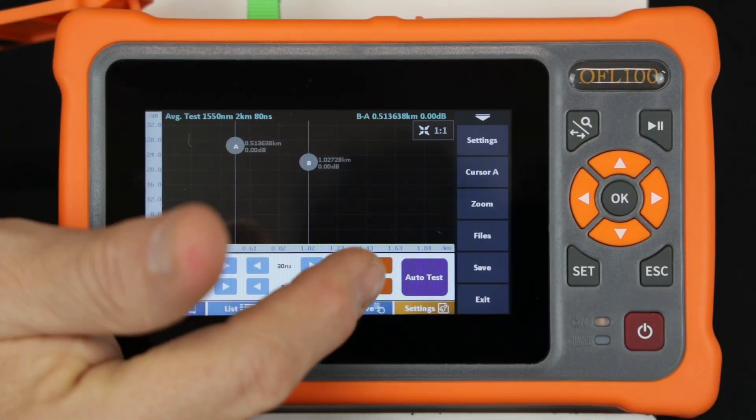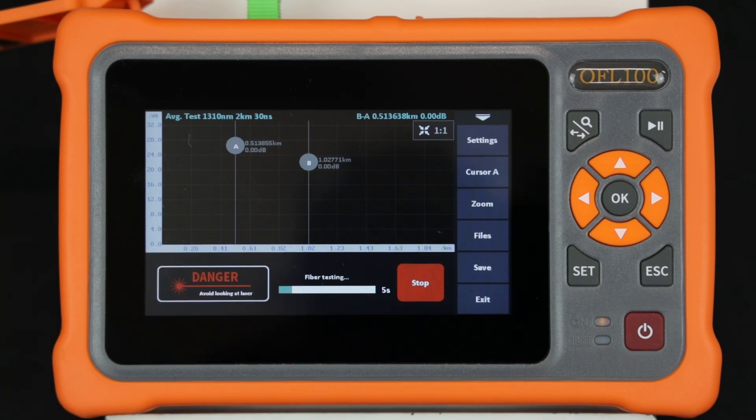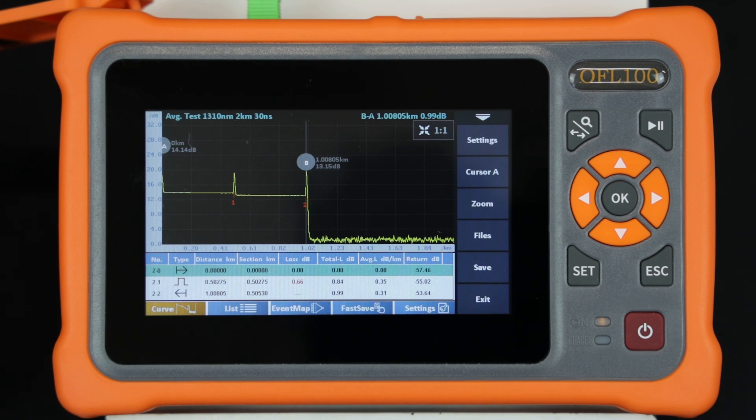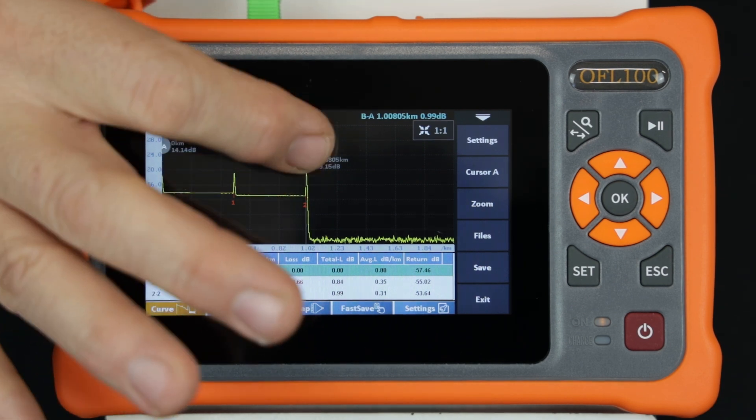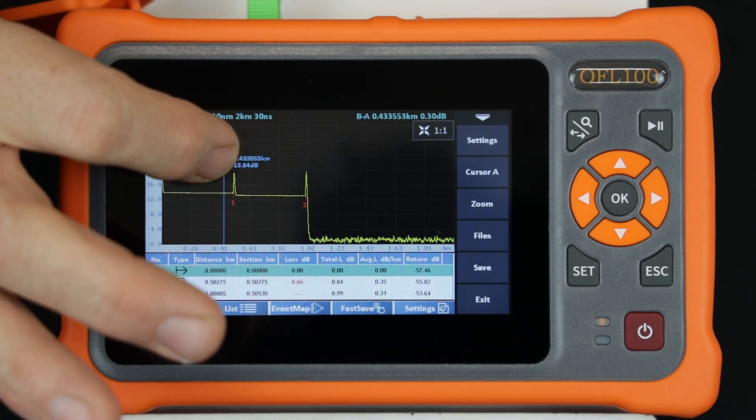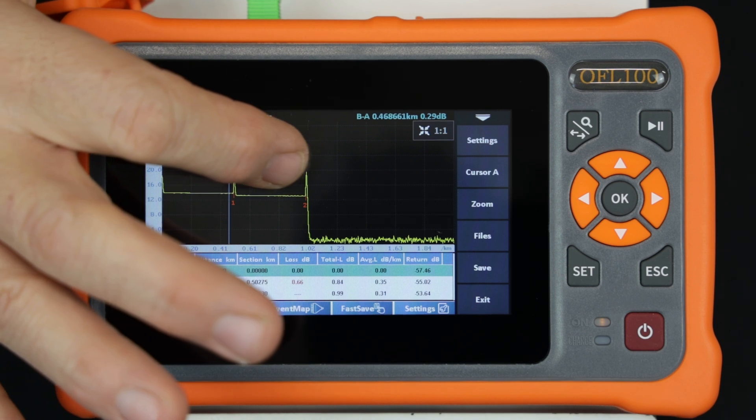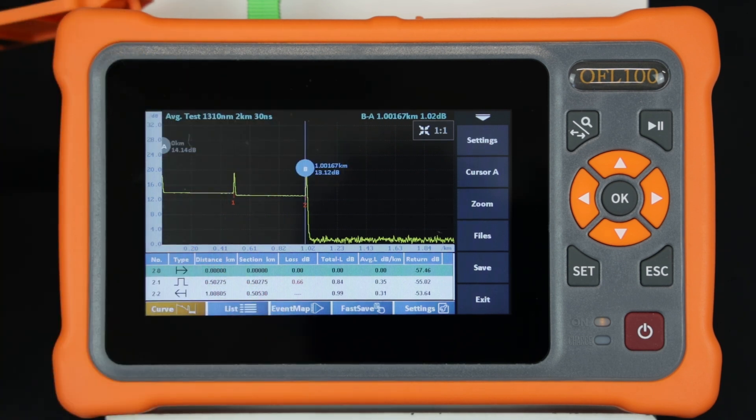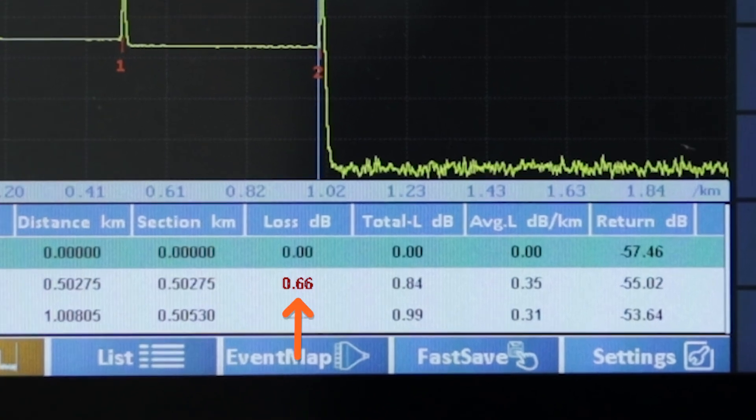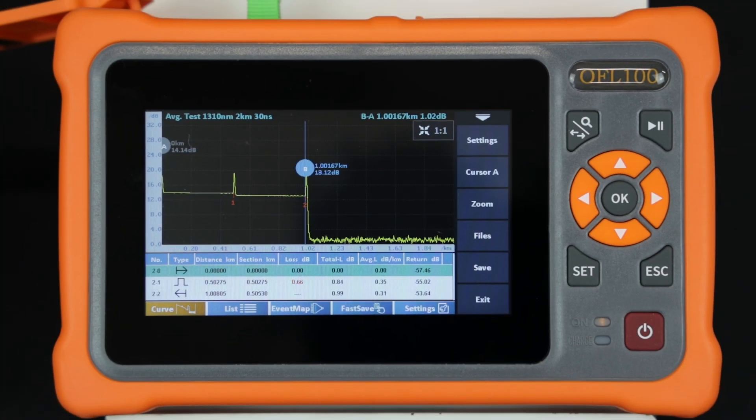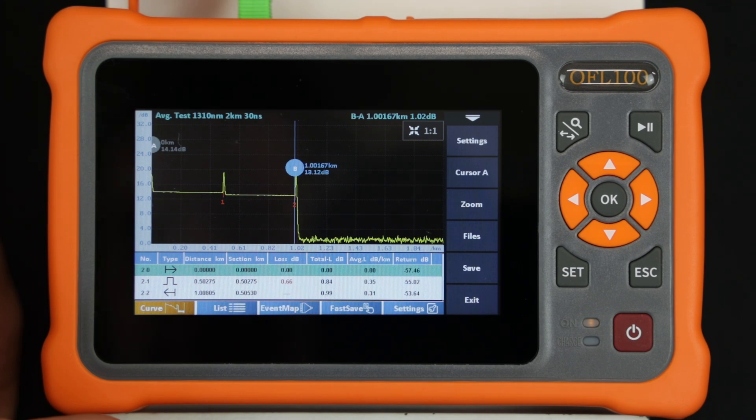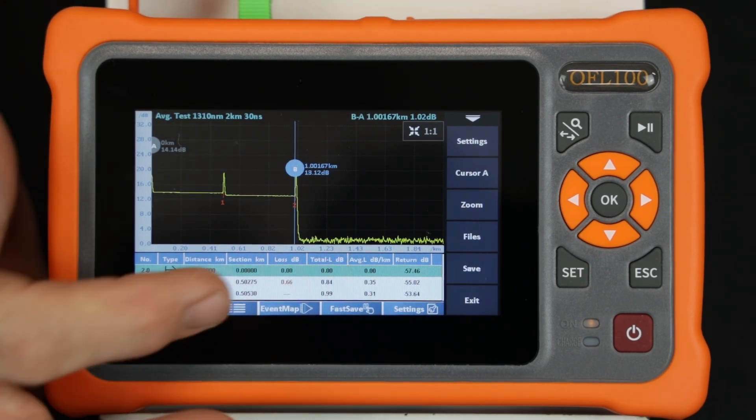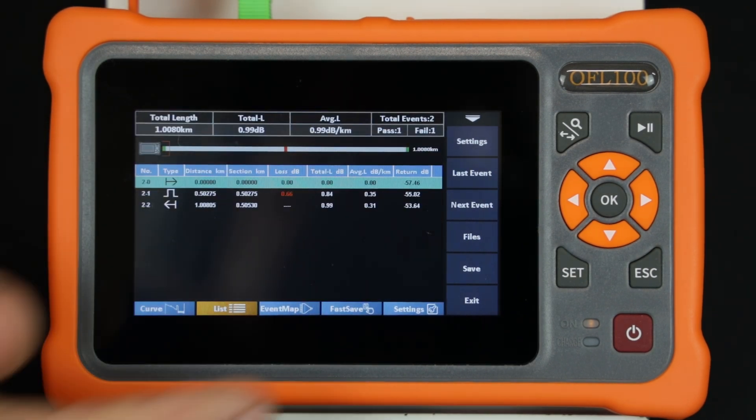Pushing the test button will start a measurement. When the measurement is complete, the cursors can be moved as desired. Under the trace display area, the events are all listed showing the measured results. Note that the loss at the connector connecting the two cables is 0.66 dB and is annotated in red. The technician can also access the list and event map views while in this mode.